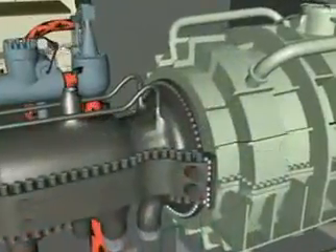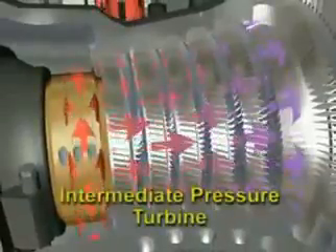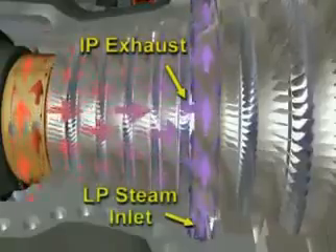The reheat steam flows into the first stage and then proceeds through the remaining five stages in the intermediate pressure section of the steam turbine. The steam flows through stationary diaphragms and rotating blades in the same manner as shown in the high-pressure turbine blading. As the reheat exits the last stage of the intermediate pressure section, it mixes with the incoming low-pressure steam and flows to the low-pressure section of the turbine.